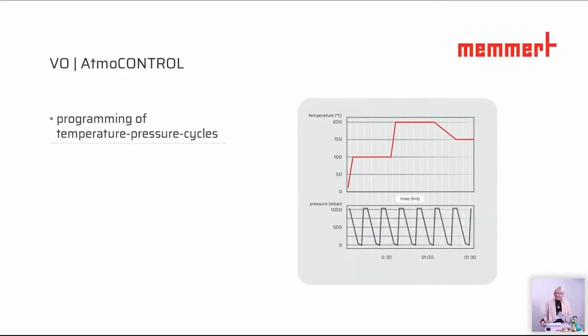So here we have a closer look at this RAMP function, which is really outstanding from Memmert. That means you can go high and low in pressure, and this is then automatically controlled. So we have the digital temperature control and the digital pressure control to be able to program defined temperature pressure cycles. We can see this in this picture. You see here, set a high pressure, then it goes down, it goes up again, and this is done automatically. And why should we do it?